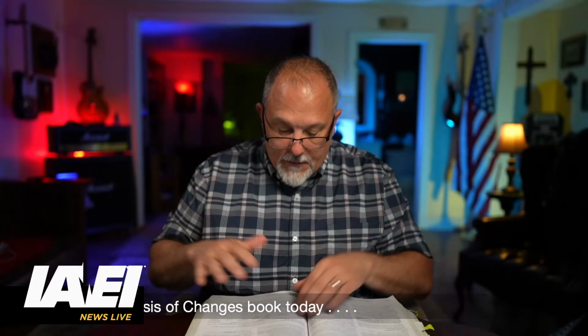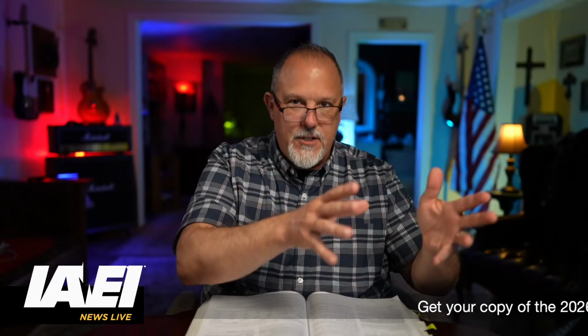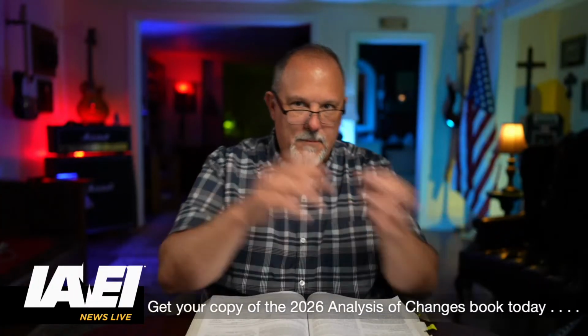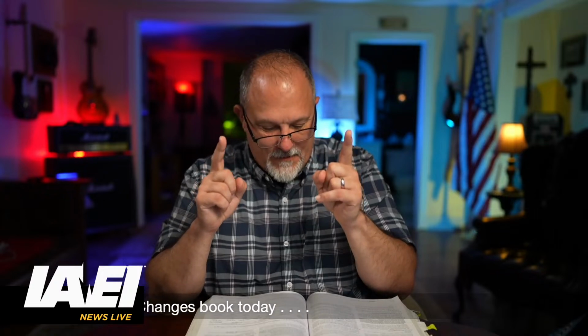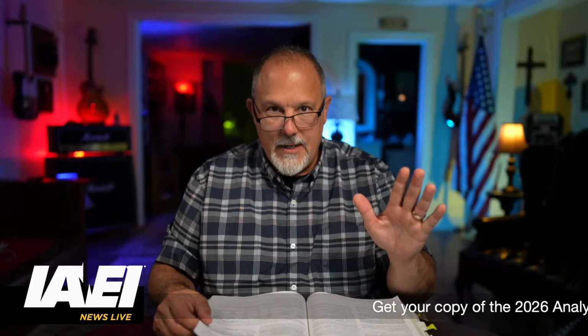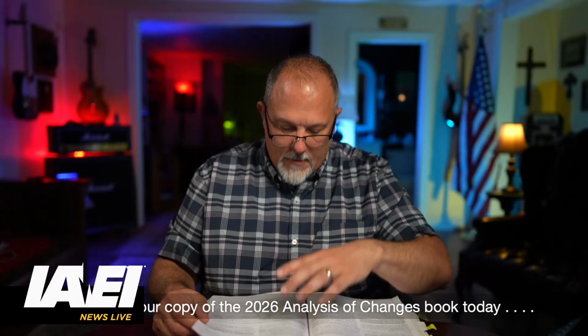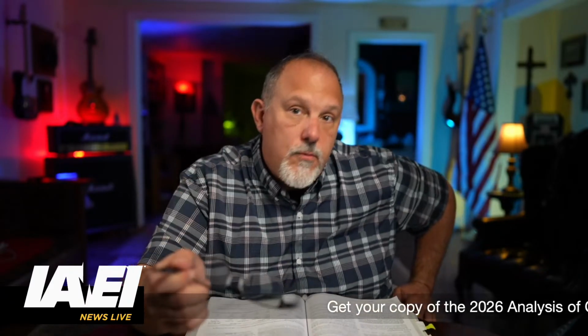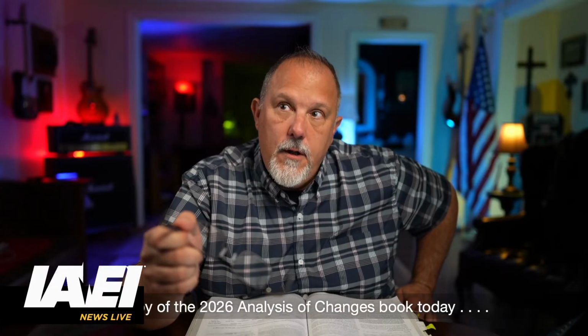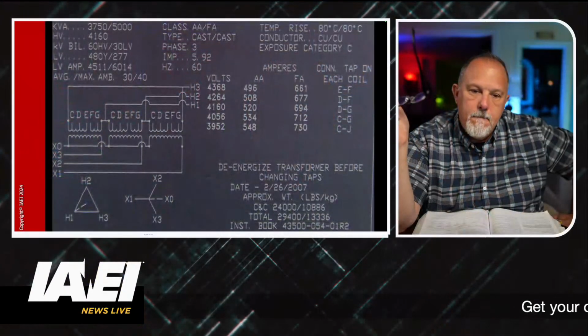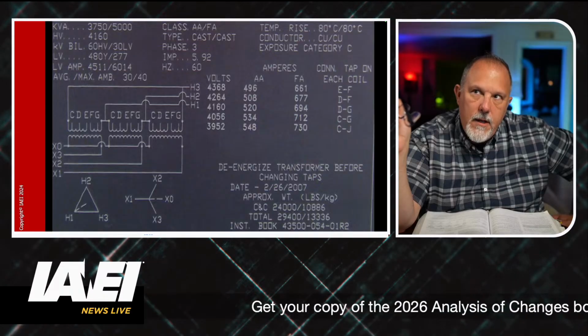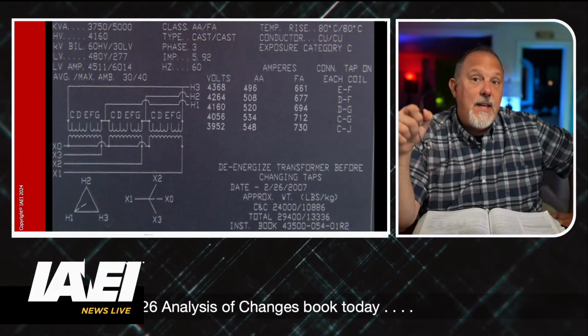And they do it backwards. In all the other articles of the code, they do low voltage first and then medium voltage is last. Not in table 450.3, because A is medium voltage and then B is your low voltage. So, regardless, I know I have these requirements in 450 for a medium voltage transformer. They talk about sizing the primary overcurrent protective device and the secondary overcurrent protective device, but they don't, Andrew, they don't tell me how to handle a transformer that has fans and it has 2 kVAs. Which kVA do I use?